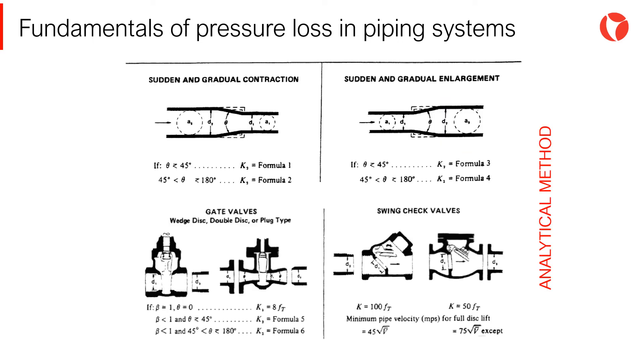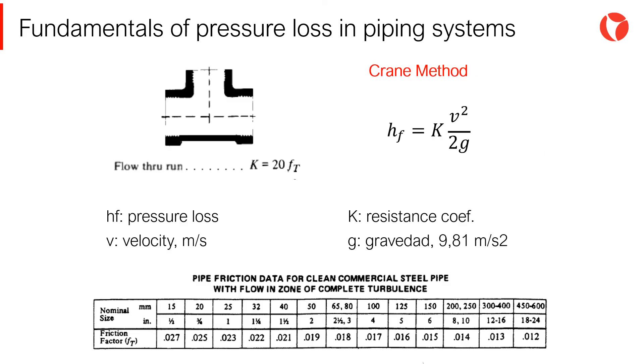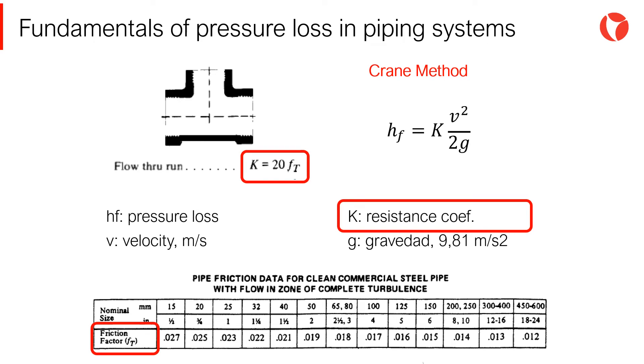Once the pressure loss in straight pipe runs has been determined, the pressure loss in fittings must be calculated depending on the system configuration. One of the most used methods to determine the pressure loss in fittings is the analytical method developed by Crane. Based on numerous laboratory trials and geometric likeliness of different fittings, this method establishes the friction factor for different sizes of new commercial piping, from which a resistance coefficient for each fitting can be obtained. Combined with Darcy's equation, this yields the pressure loss of the fitting. The great advantage of this method lies within the programming possibilities, saving a considerable amount of time.